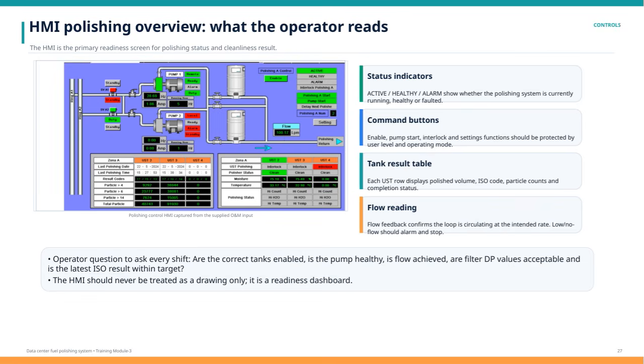The tank result table displays detailed polishing data for each underground storage tank, including polished volume, ISO cleanliness codes, particle counts, and completion status. This provides a clear view of how effectively the polishing process is proceeding. Flow reading is another important element. The flow feedback lets the operator confirm that the circulation loop is running at the intended rate. If flow is low or stops, an alarm will notify, and the system should shut down to prevent damage.